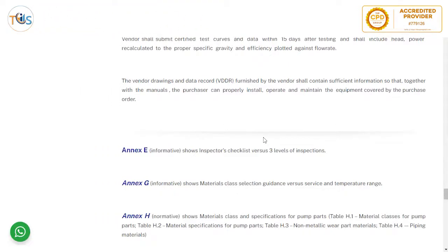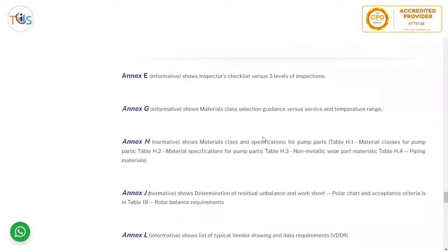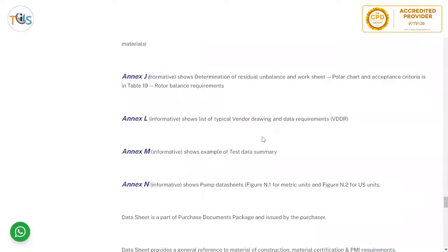Key annexes include: Annex E — inspector checklist for three levels of inspection; Annex G — material class selection guide versus service and temperature range; Annex H — material class and specification for pump parts including material classes H1 through H4 for piping and non-metallic pump parts; Annex J — determination of residual imbalance with worksheet, polar chart, and acceptance criteria in Table 19; Annex L — informative list of typical vendor drawing VDDR requirements; Annex M — example of test data summary.